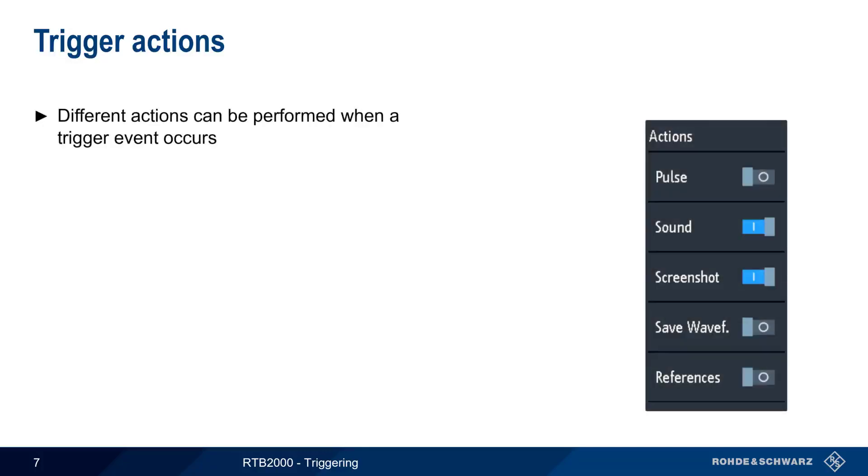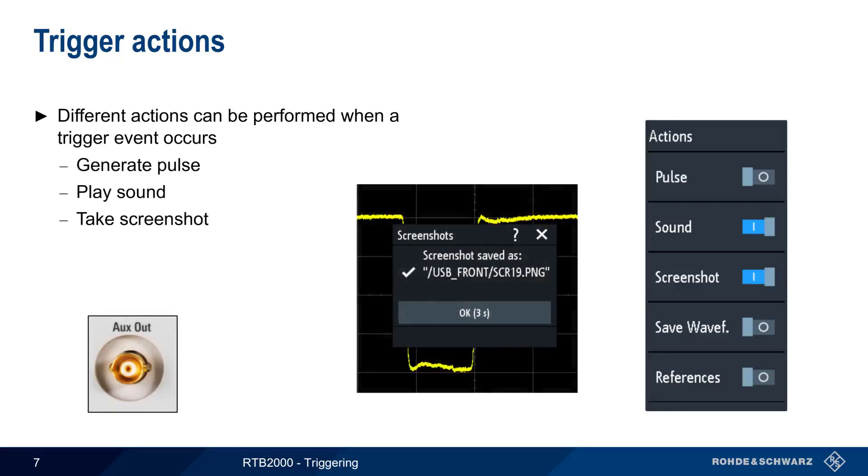The Setup menu is used to define which actions, if any, should be taken when a trigger event occurs. These include generating a pulse out on the aux out connector, playing a sound, taking a screenshot, saving the actual waveform data itself, or saving a reference waveform. These actions can also be combined. For example, the RTB could take a screenshot and play a sound when a trigger occurs.